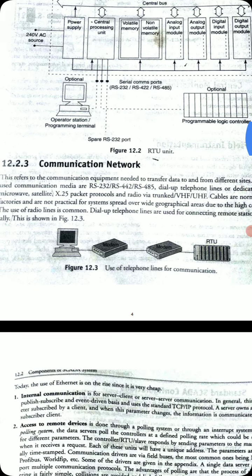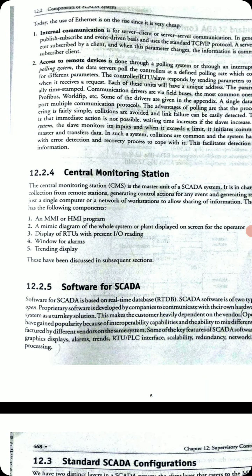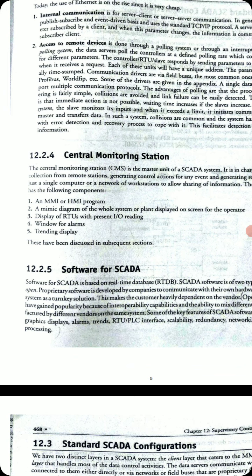Next, coming to the central monitoring station. The central monitoring station is the master unit of the SCADA system. It is in charge of collecting information from the remote stations, generating control actions for any event, and generating reports. It could be just a single computer or a network of workstations to allow sharing of information. The components of this central monitoring station are the MMI or HMI, which is man-machine interface or human-machine interface, and a mimic diagram of the whole system or plant displayed to the operator. There is a display of RTUs with present IO readings, that is input output readings, a window for alarms, and a trending display, like the share markets, showing how the trends are, what is happening, and so on.